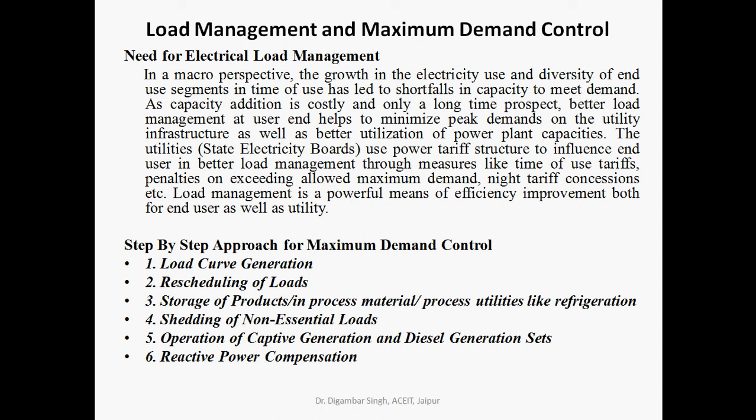The step-by-step approach for maximum demand control includes: load curve generation, rescheduling of load, storage of products, staggering of non-essential load, operation of captive generation and diesel generator sets, and reactive power compensation.